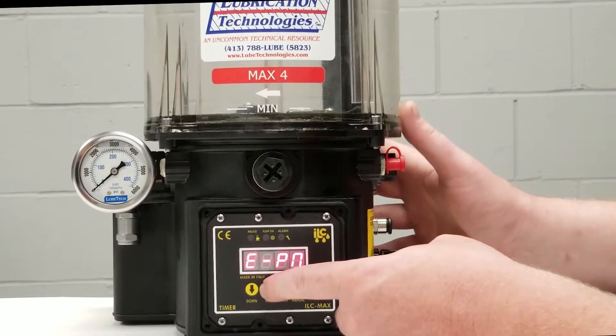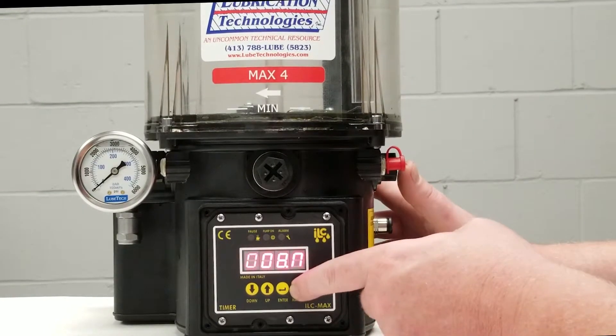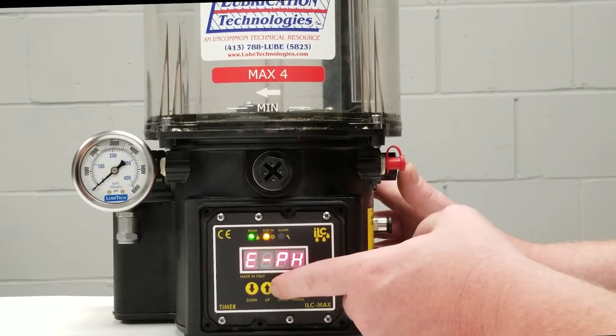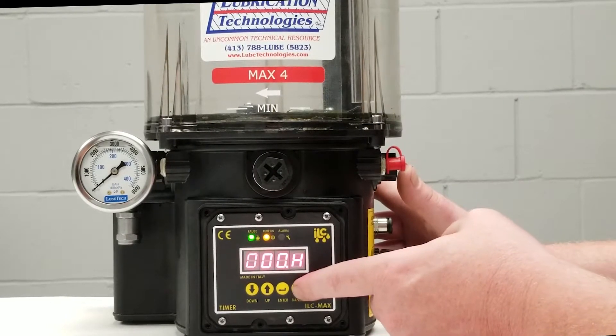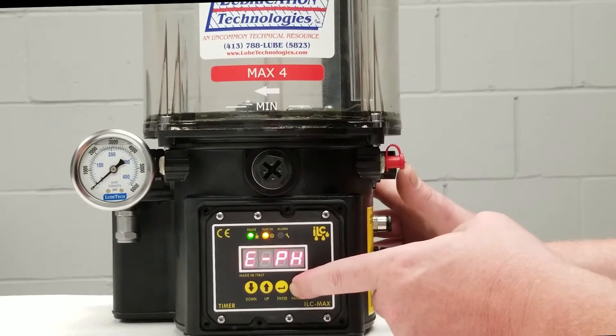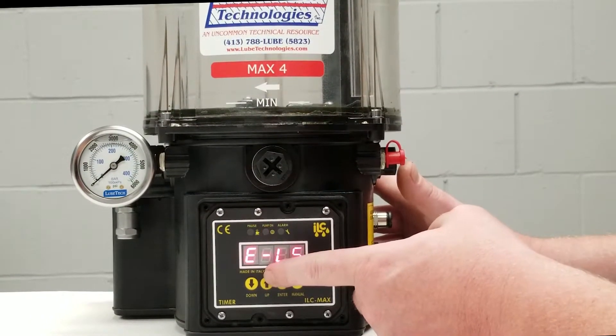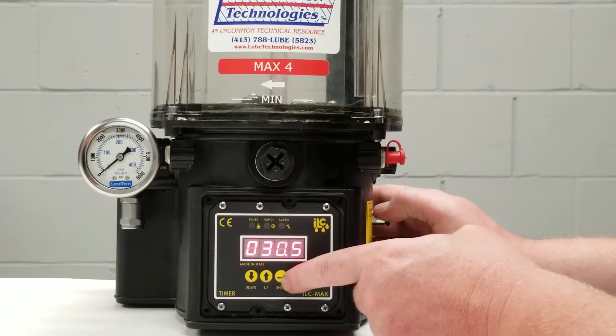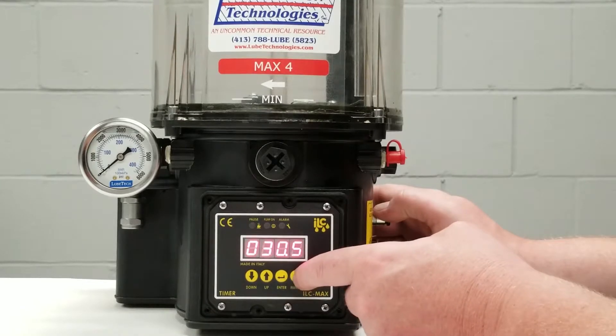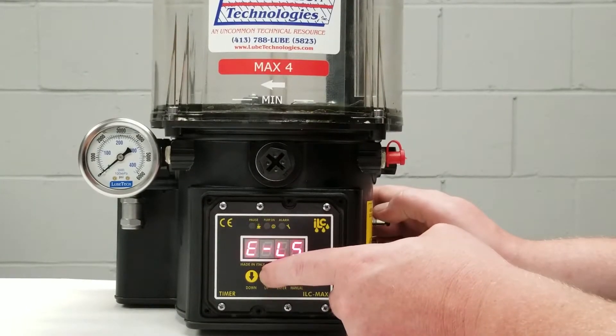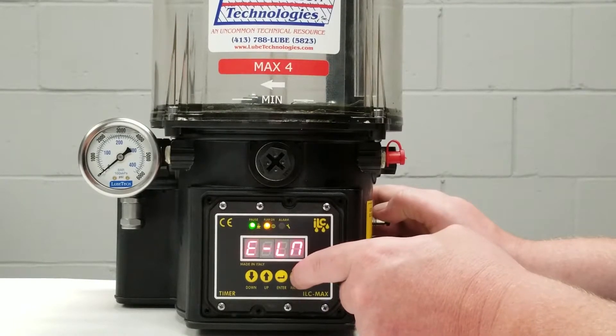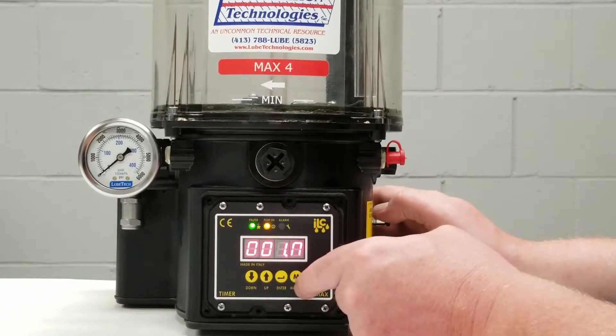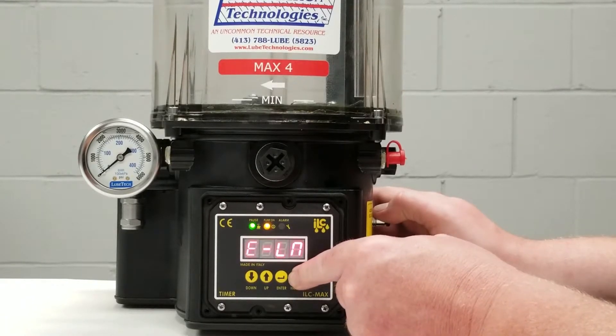Once we're there we're going to go ahead and press our M button and then we're going to press the up key. E-PN would be my pause time in minutes which is eight minutes. E-PH would be my pause time in hours which we have no hours programmed into this pump and go back out to the programming mode. E-LS, this is my work time in seconds. E-LN is our work time in minutes. This is our work time in seconds as you can see we have 30.5 seconds on the screen. We're going to leave that on there. So we're going to go ahead and we're going to add one minute to this cycle time. We're going to come out to the programming mode.